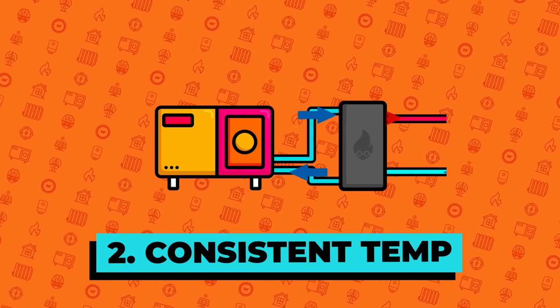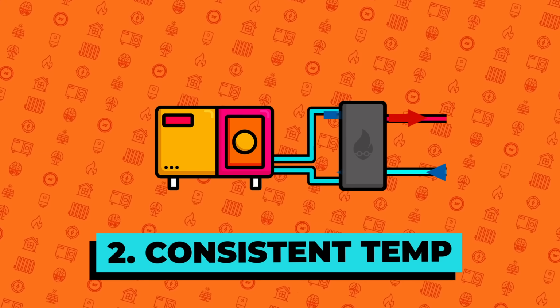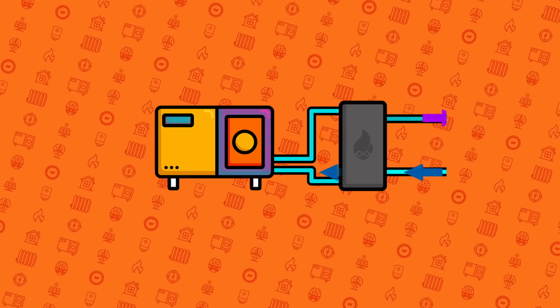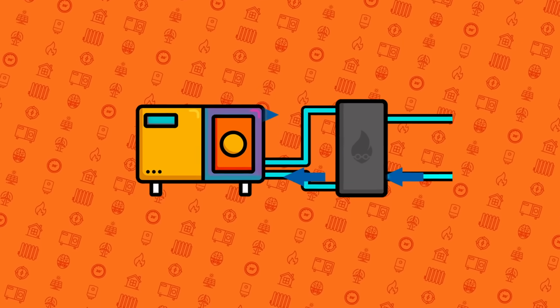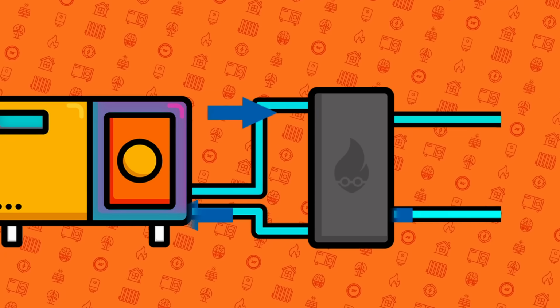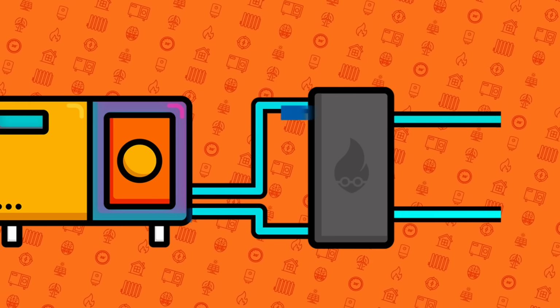1, a huge risk of severely scalding people, as this will likely be stored at well over 60 degrees. And 2, as soon as the heat pump turns on and attempts to send heat to the plate heat exchanger, it will instantly cool it down by pumping cooler water from the pipework and heat pump into the plate and causing the hot water temperature to immediately plummet. Being scalded immediately followed by a cold shower didn't feel like we were providing the best user experience.